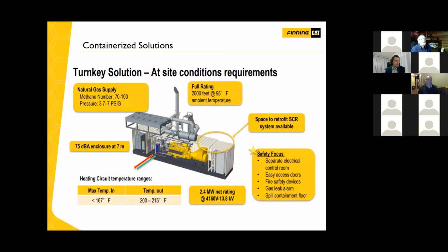So again, it's a turnkey solution, either containerized or walk-in style. Here's an example of a containerized solution with site-specific information listed. Good gas and good gas pressure is what we need—pipeline quality gas always helps a bit more than digester gas, like what we've seen at wastewater stations. We also have to make sure the engines can handle that kind of gas, so a gas sample becomes really important.